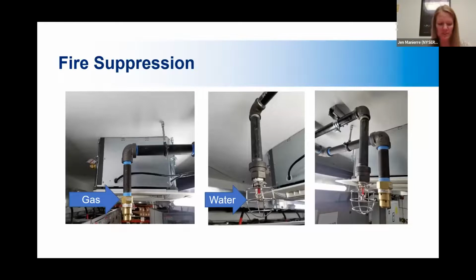There are fire suppression requirements in the code, of course. Like I said, water is definitely the best way to stop thermal runaway from happening, but you might see a combined system of fire suppression in some of these systems too, because it's not just batteries that are in there, right? There's the battery management system, and there are other things that could potentially be sparking and catching fire.